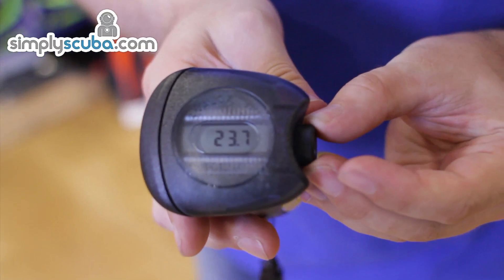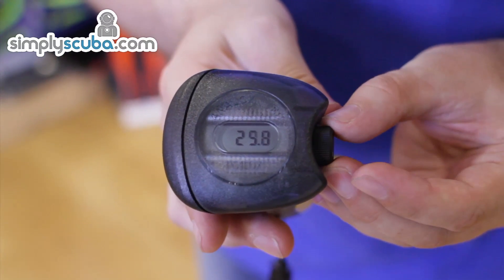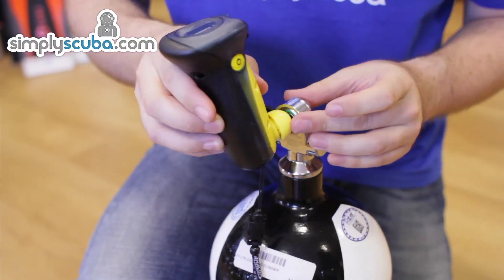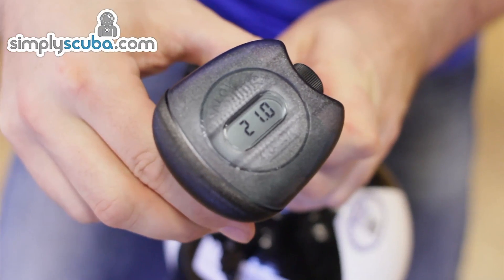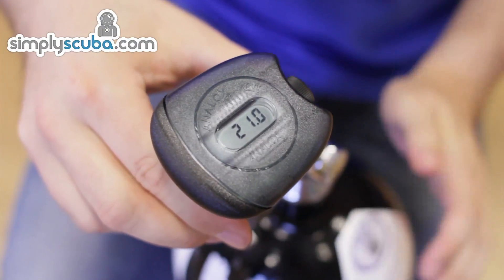User calibrated, you can control that and get that down to about 20.9. And then to analyze your mix, you just open up your cylinder just a tiny little bit, marry up the pinhole, and watch the gauge at the top. That will show you the percentage of oxygen in the air that you're breathing on your dive. And that's the Analox O2 Nitrox Analyzer.